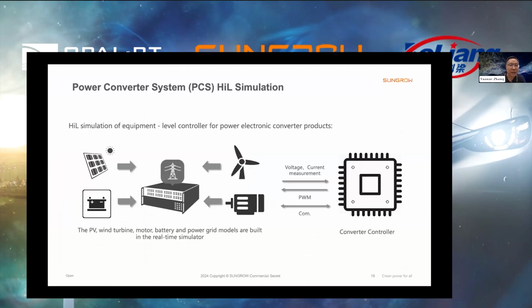We use hardware in the loop testing mainly for two types of tests. The first is individual converter controller testing. We have PV converters, energy storage converters, wind power converters, and EV drive units. We build models like PV, battery, and wind turbine in our real-time simulator, and connect their converter controller to the OPAL-RT system via I/O, DI, and communications, so we can run the whole system in a closed loop. That's the first type of simulation we do normally.